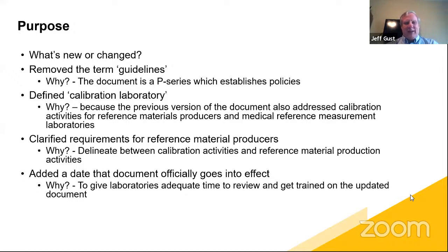We further defined what calibration laboratories were in the scope of this document, because the previous version also addressed calibration activities for reference material producers and medical reference measurement laboratories. So it did explain that this could be used by lots of different laboratories that are doing calibration. And then we clarified the requirements for reference materials producers so that we could delineate between those activities and the reference material production activities as well. And then we added the date that it goes into effect because we wanted to make sure that people had adequate time to train, understand this document, and get it in place.